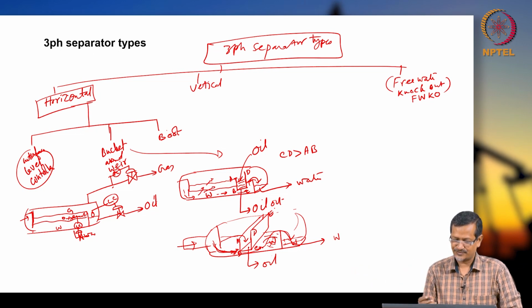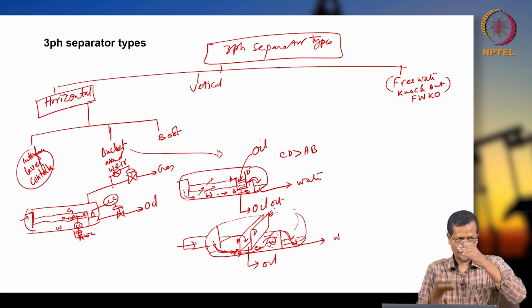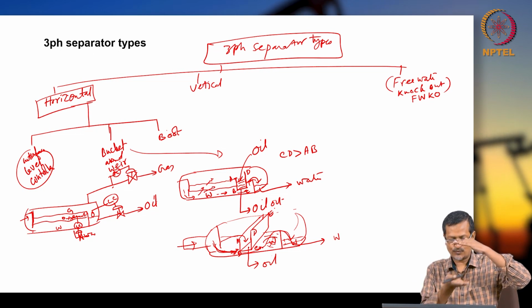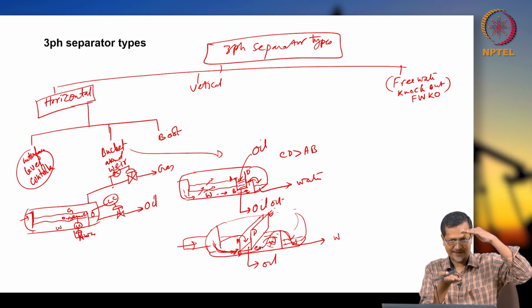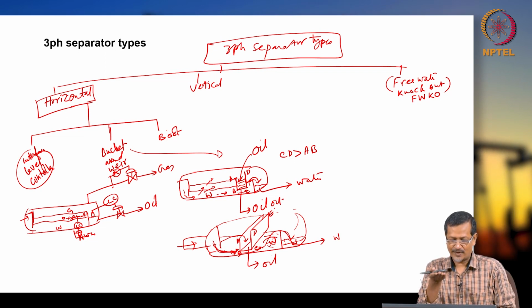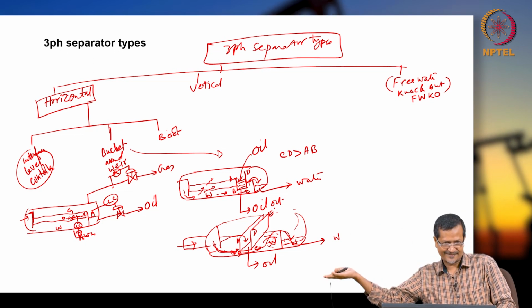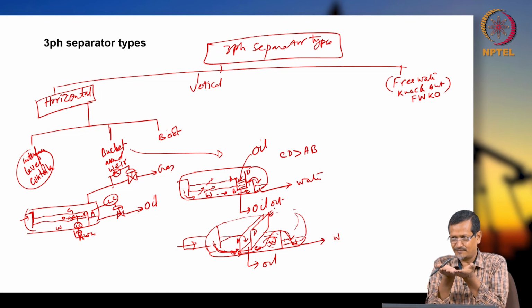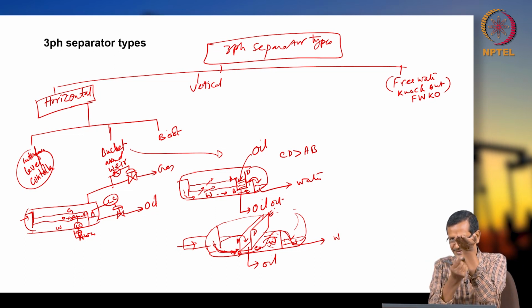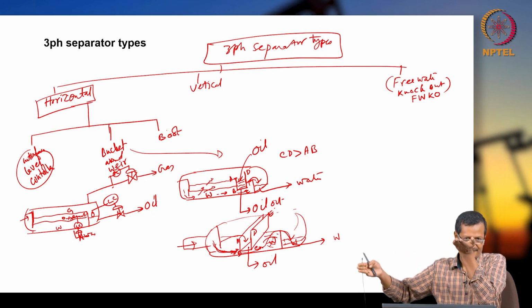So your design should be like this. The bucket bottom portion will be lower than the water oil interface. Then water will be entering below the bucket, then it will cross the weir. But if your bucket bottom part is higher than the water oil interface, then oil also will go through this and it will cross the weir. Fine.